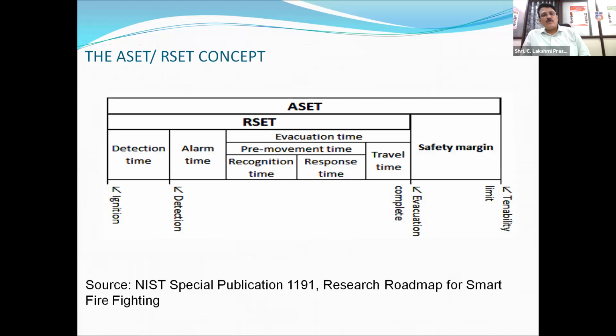In the performance-based design, by fire modeling they arrive at the available safe exit time and the required safe exit time, or ASET and RSET. ASET is the available safe exit time, and RSET means required safe exit time. This required safe exit time should be less than the available safe exit time. See, the safety margin is in between.